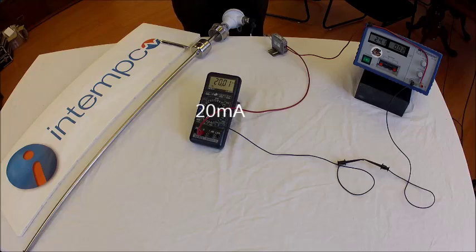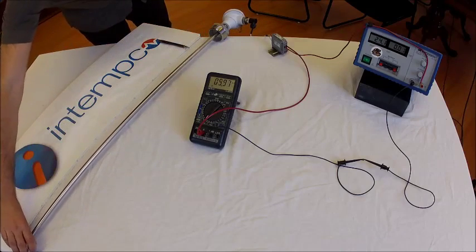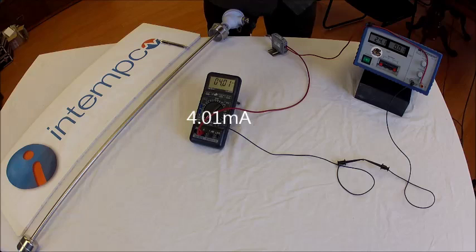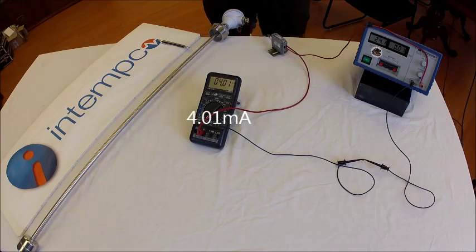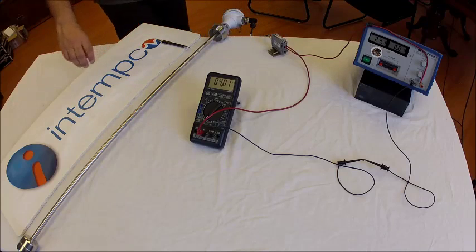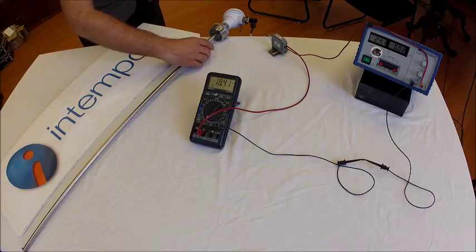Now you have to adjust the zero point after making each span adjustment. So we'll bring it down to zero again. 4.01, close enough. It may take a couple of passes until both are at their desired measurements. So now we're just going to go back up to the same position so you can see that this is 20 milliamps again.